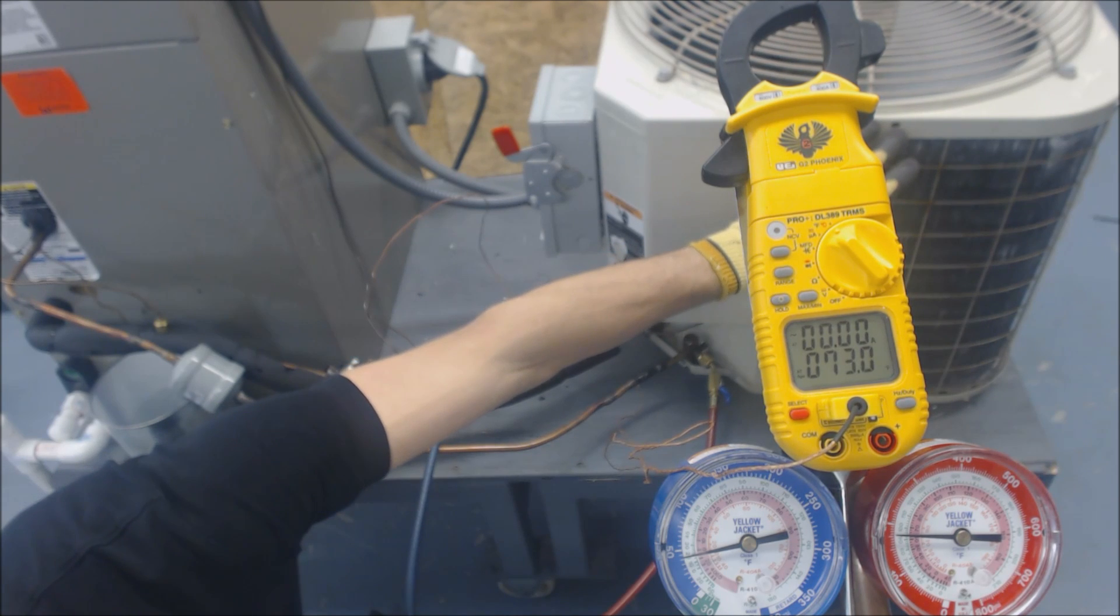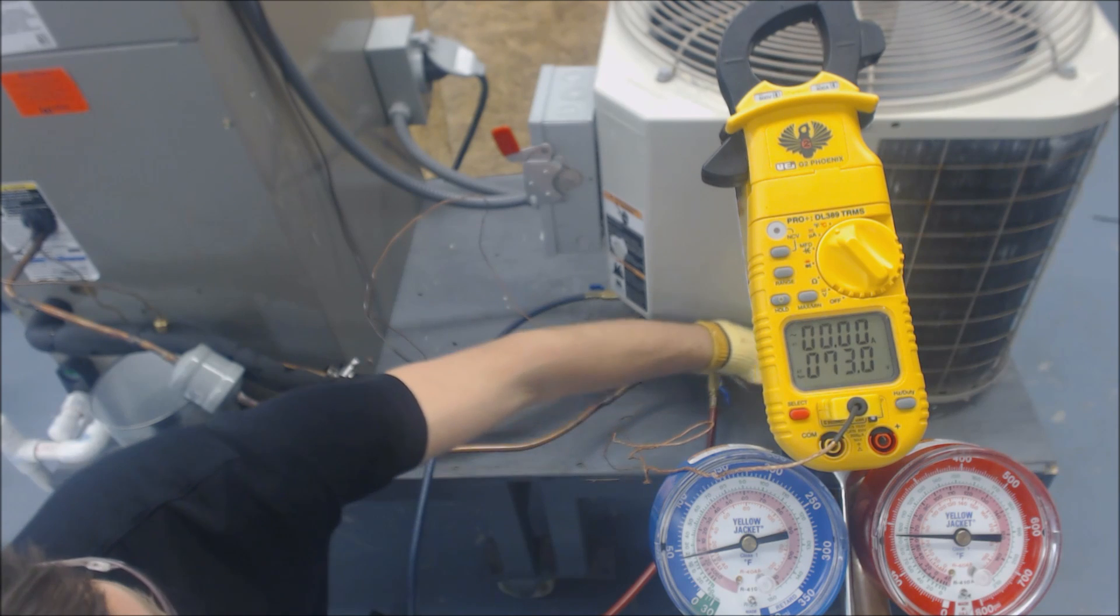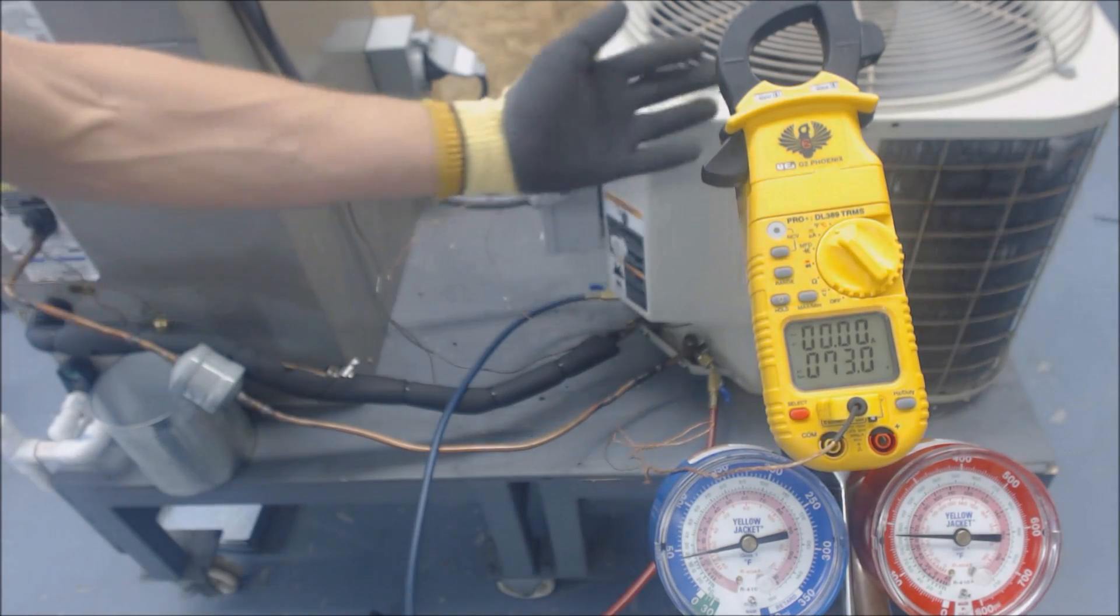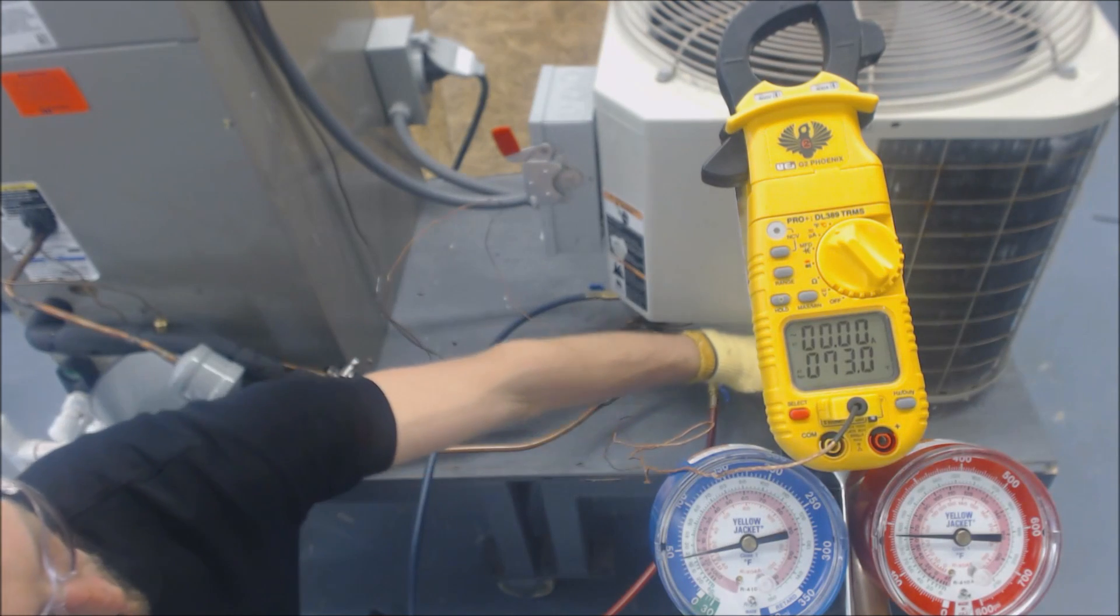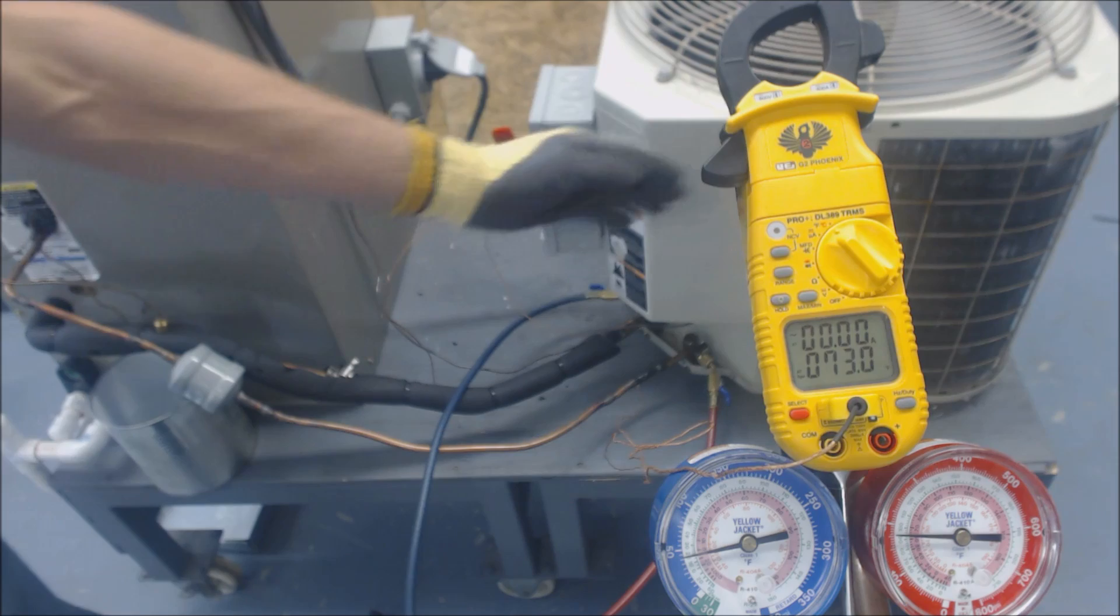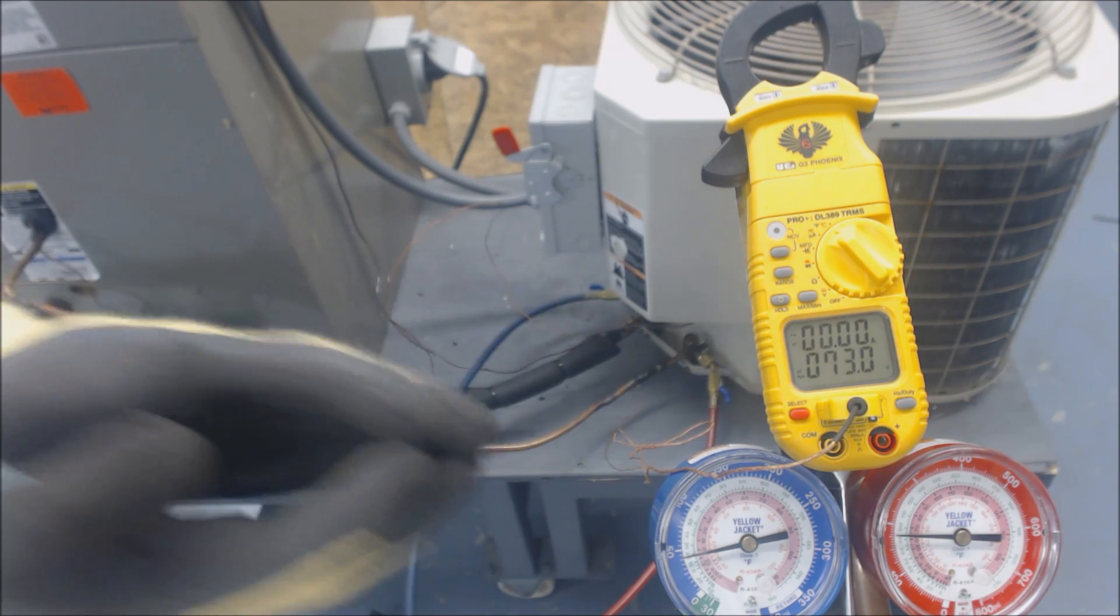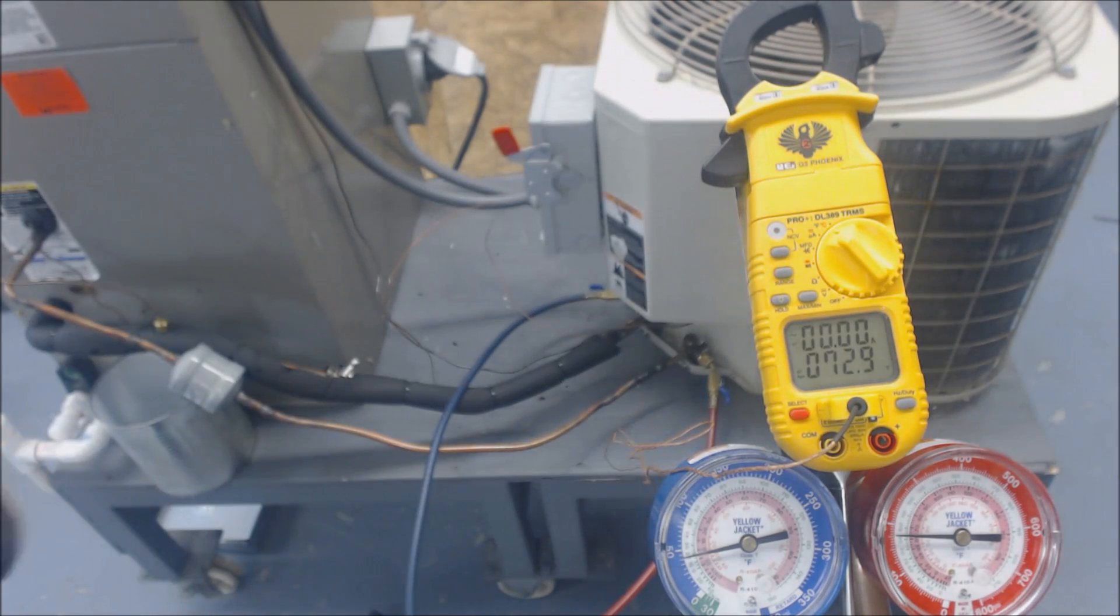There's less refrigerant in the evaporator coil, so where does that refrigerant go when it's not being used? It has to be stored in liquid in this condenser coil. Say you had your superheated vapor coming out of the compressor, then in its saturated state where both liquid and vapor exist, and then down here was your liquid. The subcooling is the temperature decrease. If it had six passes in the condenser coil left to drop the temperature of the liquid refrigerant, well now since it's more full of liquid, say it has eight passes to go. Eight passes through this coil is going to make the temperature lower and create higher subcooling. 94 degrees saturated minus 73, so you have 21 to 22 degrees of subcooling where before you had 15.